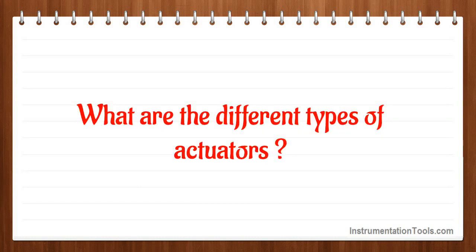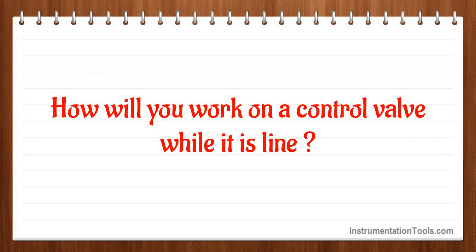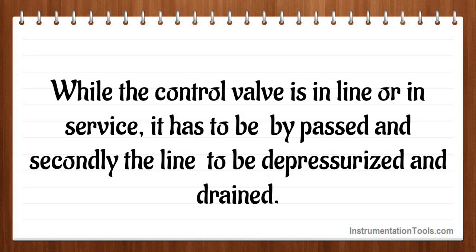What are the different types of actuators? The different types of actuators are diaphragm operated, piston operated, and electrical operated. How will you work on a control valve while it is in line? While the control valve is in line or in service, it has to be bypassed, and secondly the line has to be depressurized and drained.